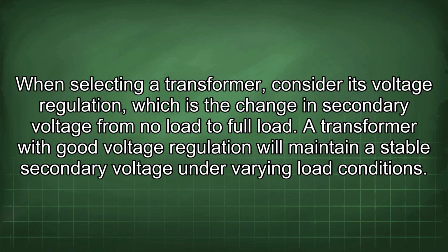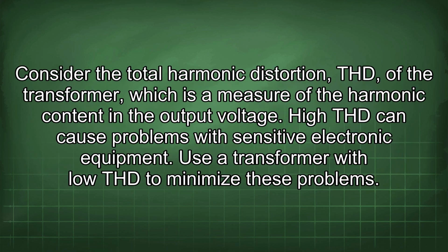When selecting a transformer, consider its voltage regulation, which is the change in secondary voltage from no load to full load. A transformer with good voltage regulation will maintain a stable secondary voltage under varying load conditions. Consider the total harmonic distortion, THD, of the transformer, which is a measure of the harmonic content in the output voltage. High THD can cause problems with sensitive electronic equipment. Use a transformer with low THD to minimize these problems.